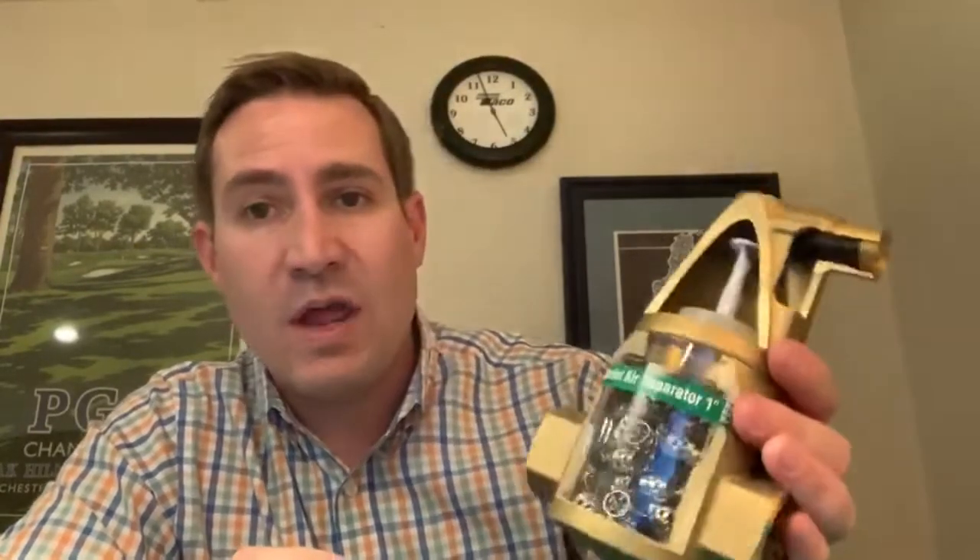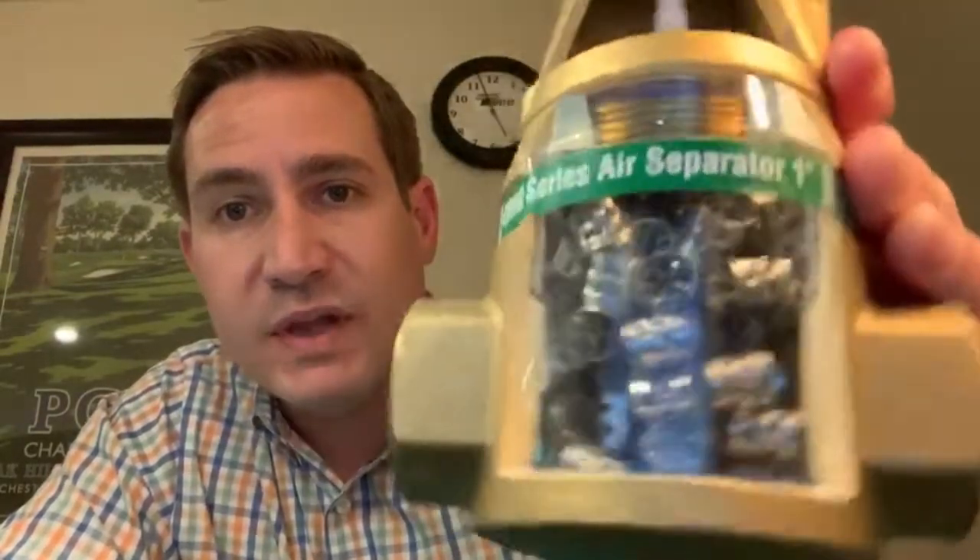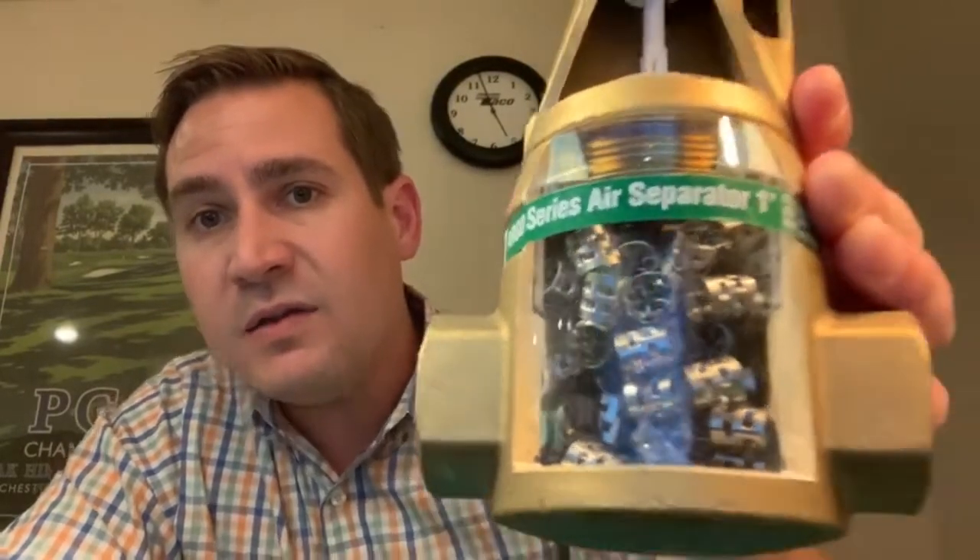One of the benefits of this product is that we have a huge amount of surface area inside of the unit, and that is due to a patented design that Taco came up with. If you can see these little stainless steel bits here, called pall rings — what that whole jumble of metal does is it increases the surface area and allows small bubbles to gather on those pall rings. Over time, as smaller bubbles start to attach and more smaller bubbles start to attach, the bubbles become bigger, break off of the pall ring, and rise to the top and get vented out of the assembly.